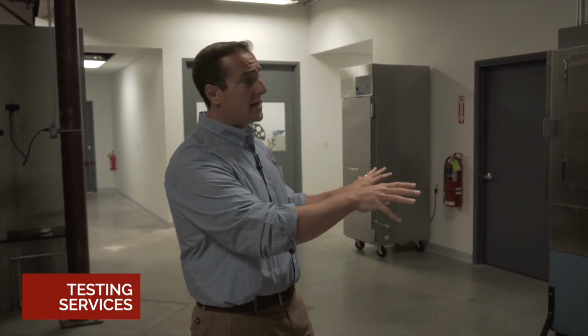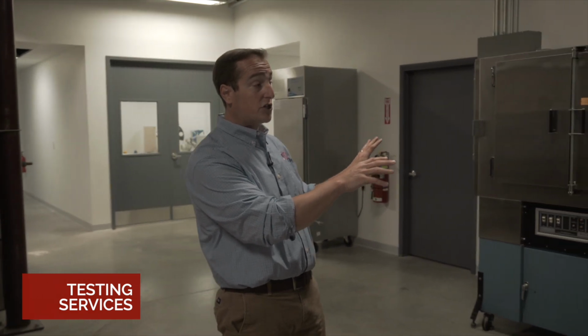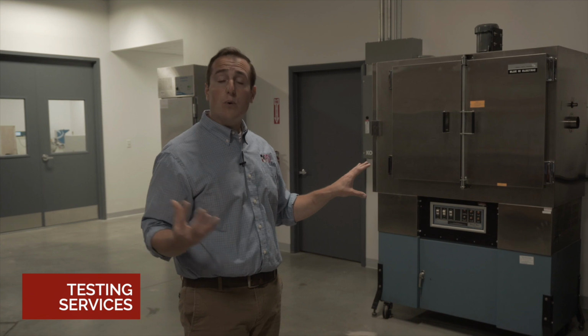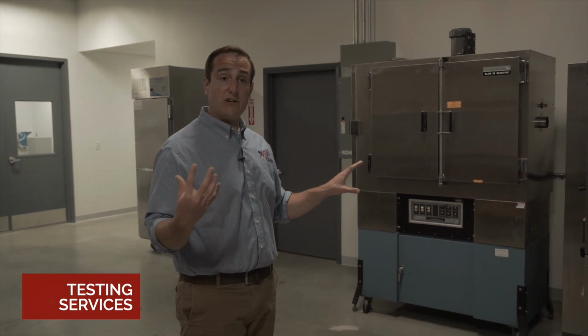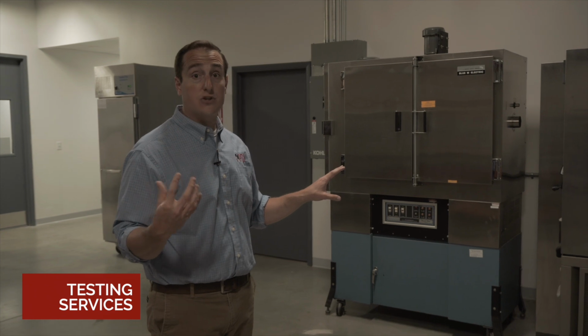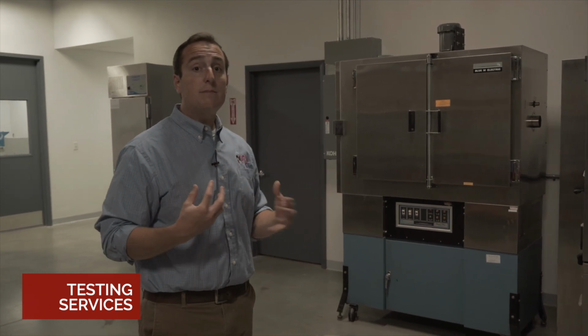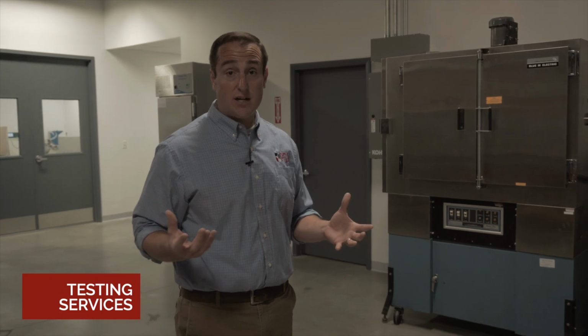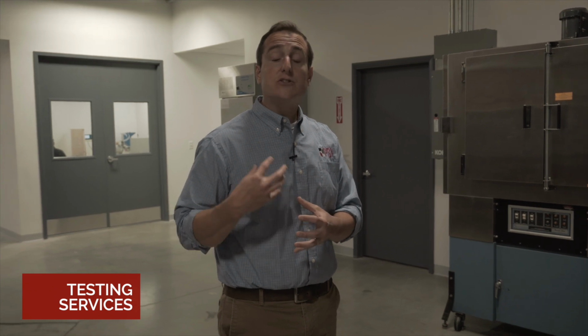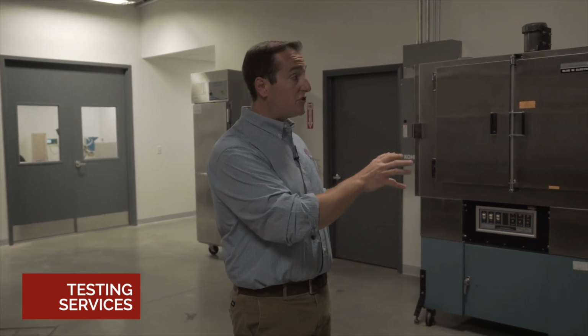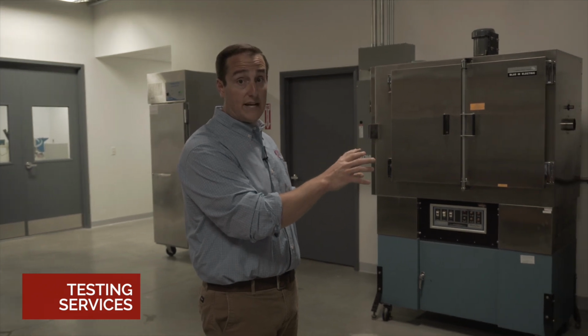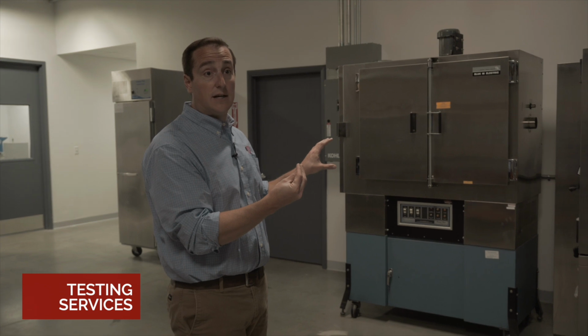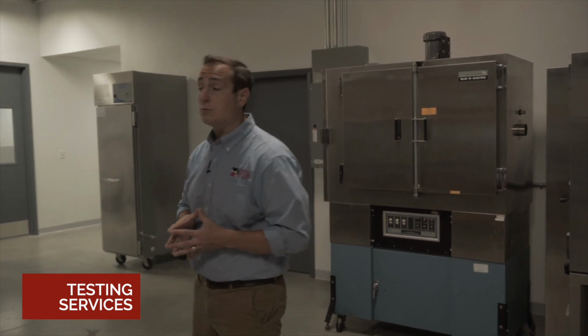These particular ovens are sat here because they do not only temperature, but they also can do humidity. A lot of what we do is in the medical space. And one of the catchphrases in the medical space, or the testing that is required, is called extractables and leachables. So if I'm designing a medical device that's going to be patient contacting, you need to be very aware of what is in that material and test it thoroughly to ensure nothing comes out of that that's going to be deleterious to the person as they're using it. This allows us to artificially age and expose different polymers at different rates and at different humidities to fundamentally understand if there's an issue from a toxicology or extractables and leachable perspective.